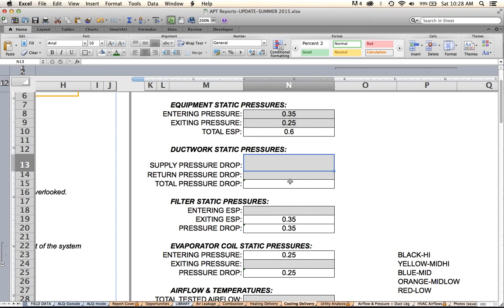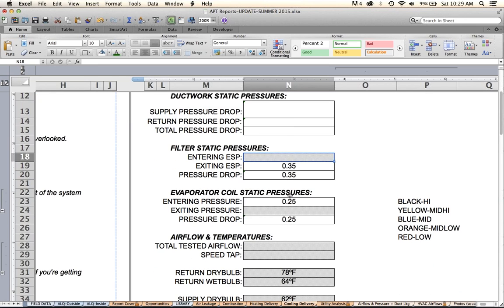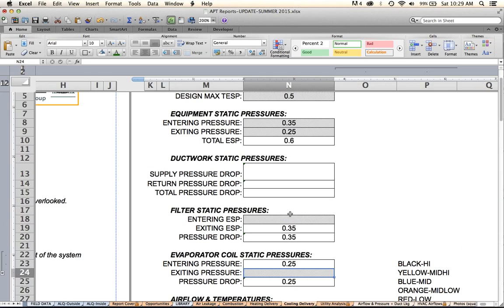The ductwork static pressures. So the supply pressure drop, and this is kind of cool. I'm going to do this real quick. Watch me work my magic. So I'm going to make both of these white, not gray, and these are going to self-populate. Bam, and bam. Okay, good. So what we just did is making our lives a lot easier. So we only have to take 1, 2, 3, 4 pressure readings. Okay, we're going to take one on the far side of the filter, the entering side of the filter.